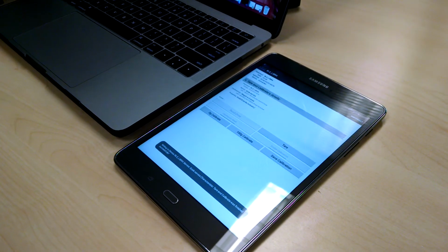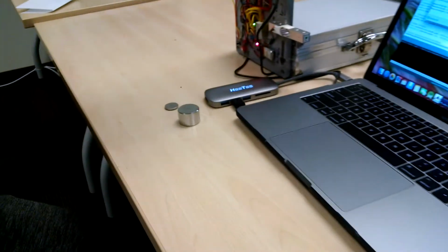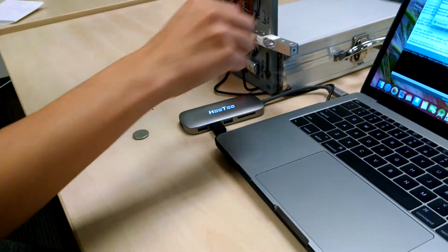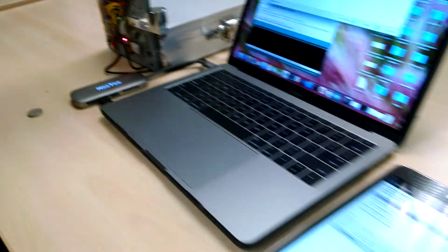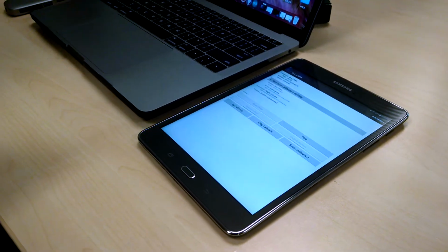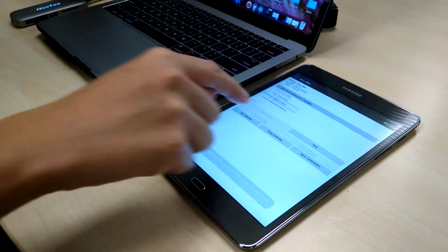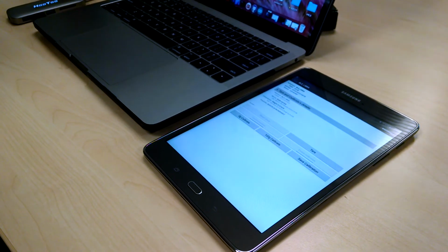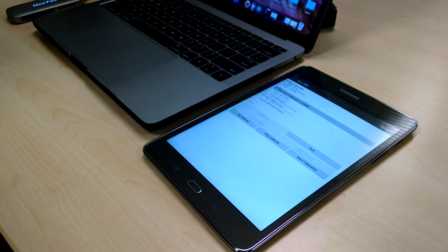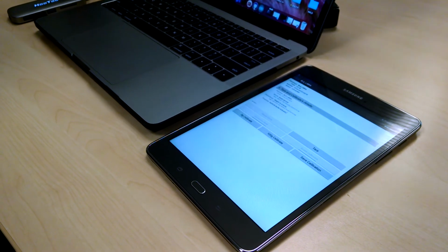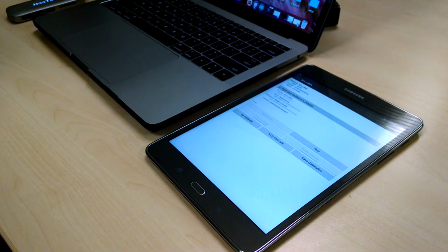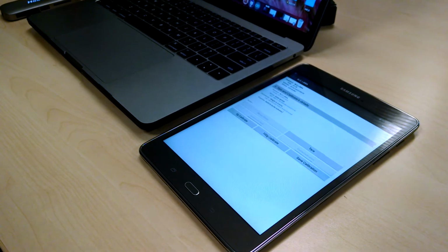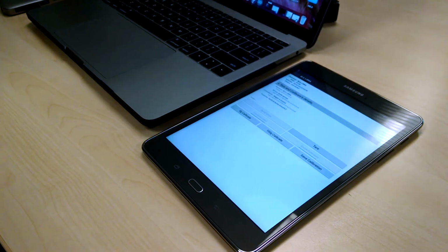After the zero point is saved into the RAM, a 100 gram calibration weight is used to set the 100 gram value. Once the 100 gram value is captured, the save function will take the value that is saved in RAM and push it up to the EEPROM so that when the scale is turned on next time, the EEPROM value will be loaded by default and this will be used.